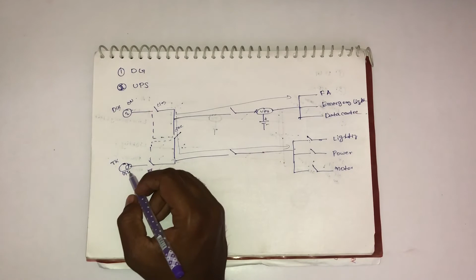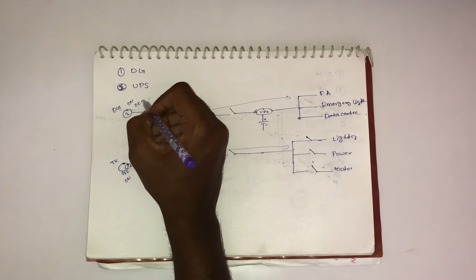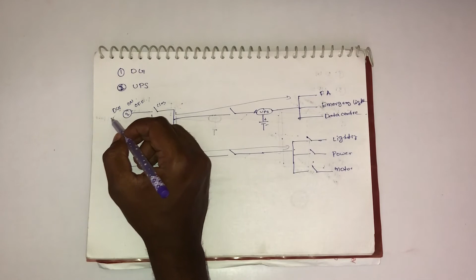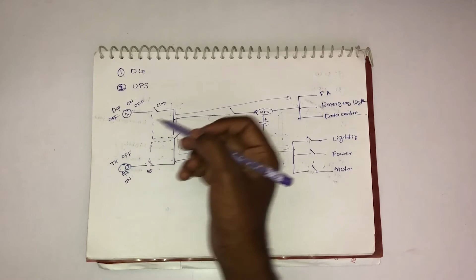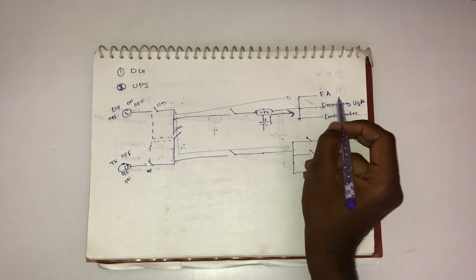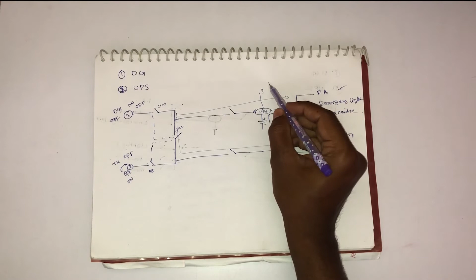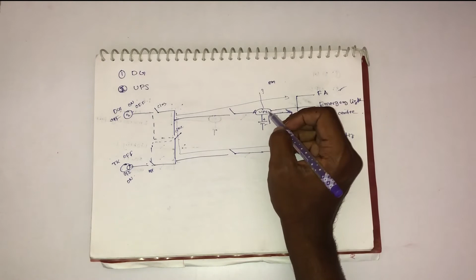In the second condition, suppose your transformer is on and the diesel generator is off. This one will close, this one closed, and this one is open. So your transformer supplies load to the emergency systems as well as the normal system. But in the case when the two sources are also off, this one off and this one off, here the UPS system, the batteries will supply power to this load and your load is continuously on. So here we are only discussing the UPS system, not a diesel generator. Diesel generator I will make a video on separately. So here we only discuss the UPS system.